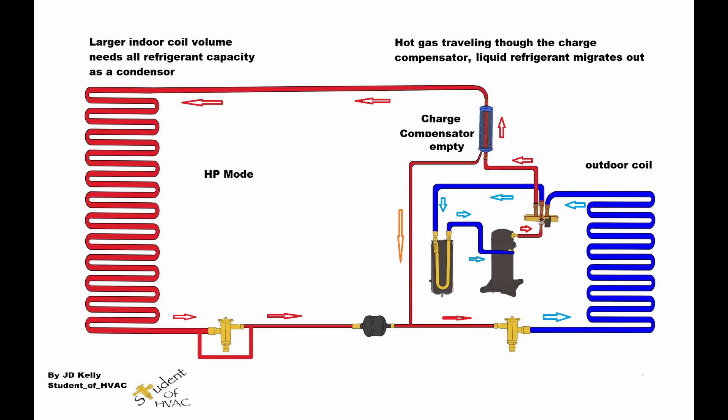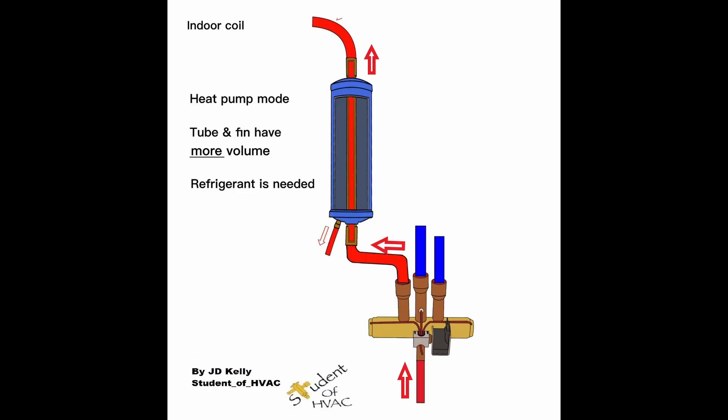So this manufacturer has moved the charge compensator between the indoor coil and the reversing valve. If we notice, the indoor coil is larger in volume, so it's drawn larger. It needs all the refrigerant during the heat pump or heating mode. As the hot gas flows through the center tube of the charge compensator, the charge compensator gets very warm. Liquid refrigerant migrates out of the charge compensator and into the system.